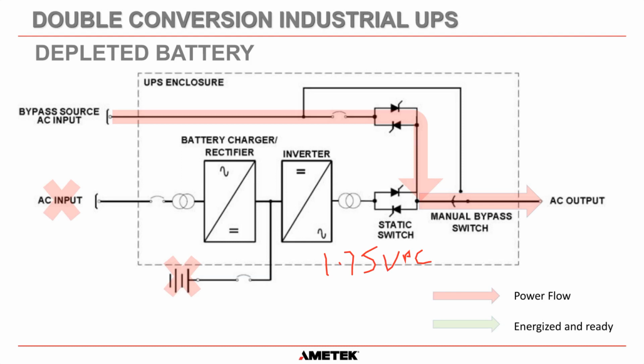So what AMETEK solid state controls do as a manufacturer, and what other manufacturers do, is that they say, okay, we're going to set up a circuit within the system, and it's actually within our inverter control board here, that's monitoring the DC into the inverter. And if you times 60 cells times 1.75, you get a voltage of 105 volts. And what the inverter control board does, it says, okay, if the DC bus goes below 105 volts, I am going to trip this DC input breaker and disconnect the batteries, because that is the only way we can protect the batteries from being over discharged.